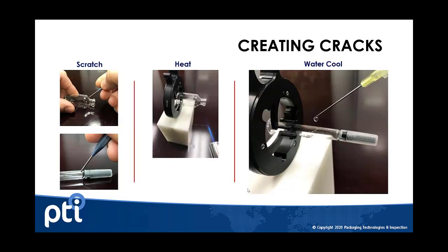Creating cracks is another great way to produce positive controls that reflect real-world defects. Use safety precautions since it involves heat and cracking the glass. The process starts by scratching the glass surface where you want to create a crack, then heating that surface for about 3 to 5 seconds, and then applying a droplet of water. That droplet creates a thermal shock and produces the crack.